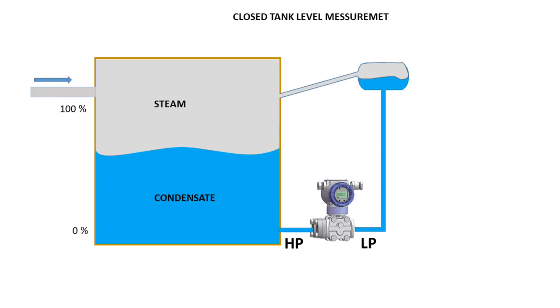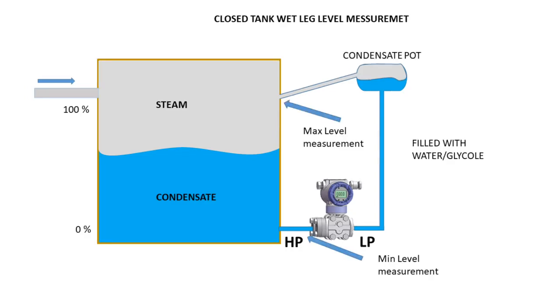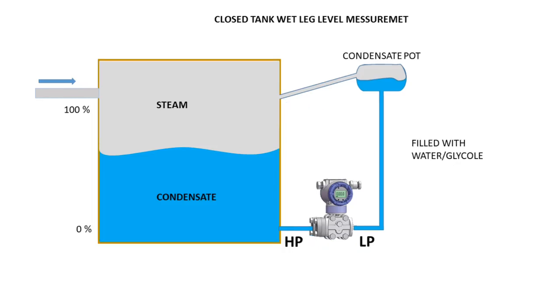First we must know the property of steam. When steam cools down it will change to water. That means the bottom of the tank will have condensate water and the steam will be at the top part of the tank. If we connect the low impulse line to the top of the tank, the steam will go through it and condensate in the line.